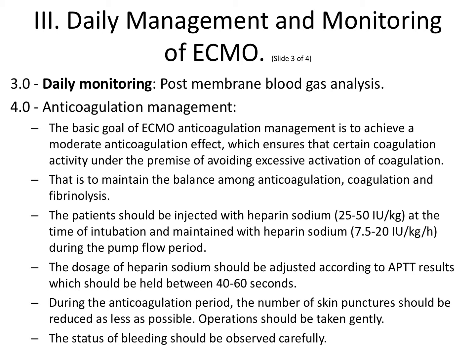4. Anticoagulation management. The basic goal of ECMO anticoagulation management is to achieve a moderate anticoagulation effect, which ensures certain coagulation activity under the premise of avoiding excessive activation of coagulation. That is to maintain the balance amongst anticoagulation, coagulation and fibrinolysis. The patient should be injected with heparin sodium 25 to 50 IU per kilogram at the time of intubation and maintained with heparin sodium 7.5 to 20 IU per kilogram per hour during the pump flow period. The dosage of heparin sodium should be adjusted according to the APTT results, which should be held between 40 to 60 seconds. During the anticoagulation period, the number of skin punctures should be reduced as much as possible. Operations should be taken gently. The status of bleeding should be observed carefully.